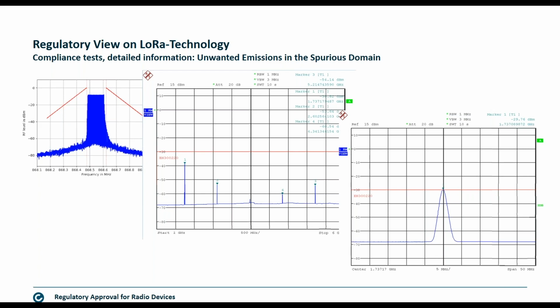So usually we would not recommend to a customer, even if this is passed by 0.24 dB, which is a very, very small figure, to concentrate on the first harmonic. This is a question of design of the device, and this definitely would need rework.